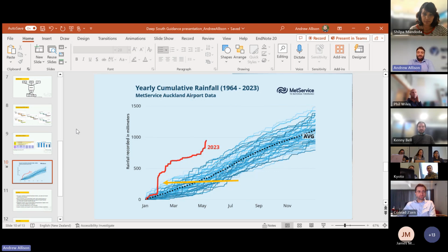As you know, last January, Auckland had a 1 in 220-year flood event, the most expensive non-earthquake event in the history of New Zealand until 3 weeks later when Cyclone Gabrielle came through. But it was about 3 months since we'd finished the modelling for the Auckland plant, and the Helensville wastewater treatment plant ended up behaving basically exactly as our model suggested it would. The Kaipara River burst its banks upstream from Helensville. It inundated large areas of farmland, but the peak river flows coincided with the lower portion of the tidal cycle, at least not the peak of the high tide. So the plant was not overtopped by combined river flows and surge.